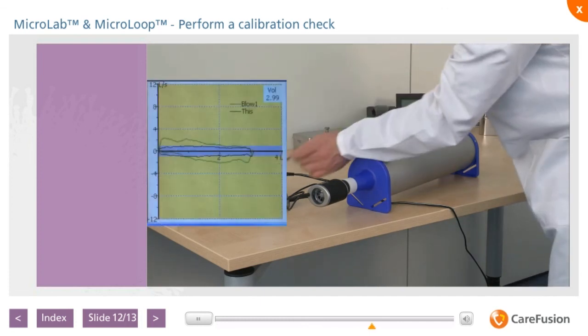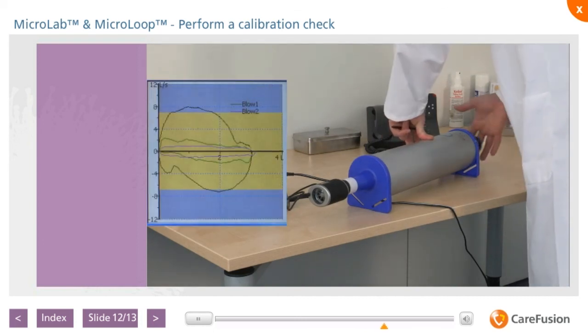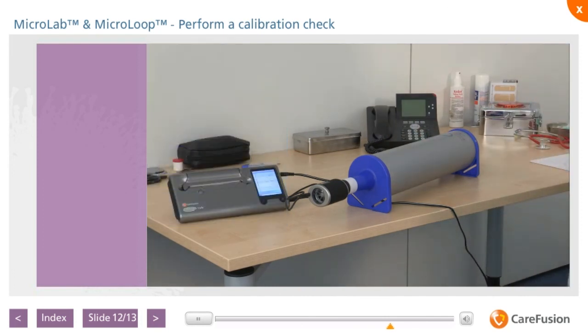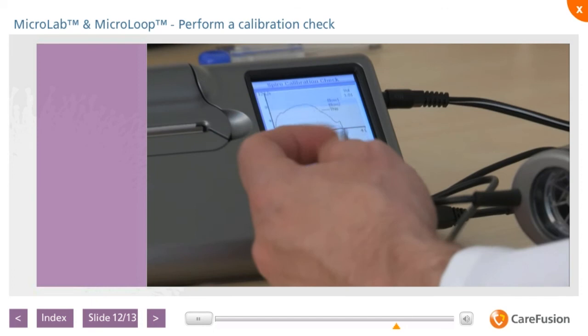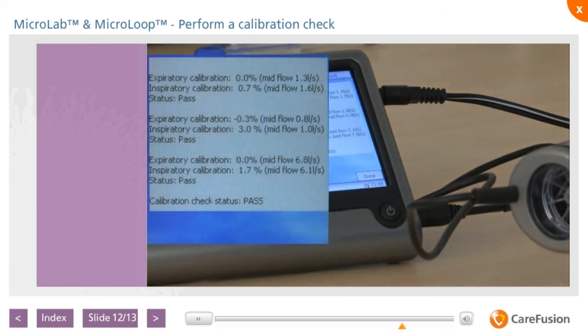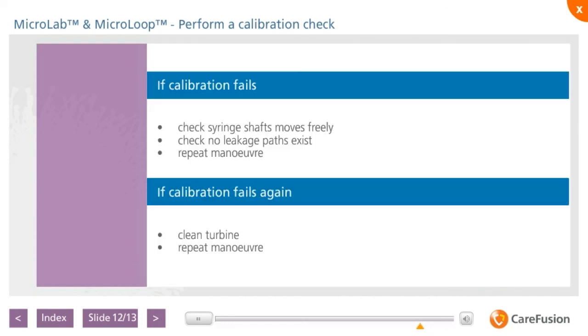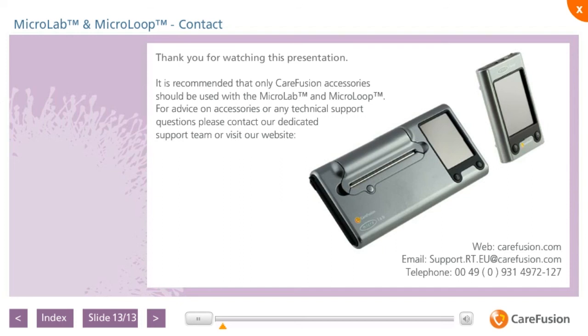Once the maneuver has been completed, select Next to move to the next flow rate, where the grey bands will guide you as to the speed the syringe should be emptied and filled. When all 3 flow rates have been performed, the display will show a report of the inspiratory and expiratory flow rates for each calibration band with a pass or fail status. The spirometer should pass on each flow rate. Should calibration fail, then repeat the maneuver, checking that the syringe shaft is moving freely and that there are no leakage paths. If calibration continues to fail, then clean the turbine as per the instruction manual and then repeat the calibration check.